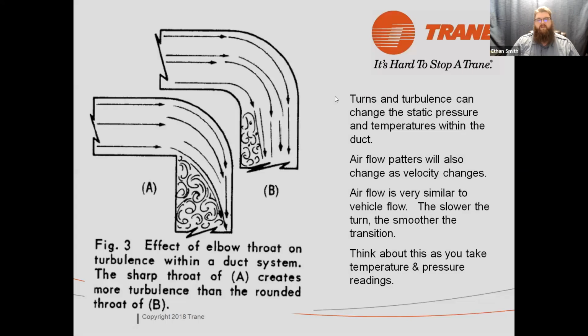Okay. It is important when you're looking at positioning those pitot tubes that you get them out of any areas of turbulence. So when you're near fittings, you want to be downstream. The general rule of thumb is you want to be 2 duct sizes downstream of any fitting or directional change in your ductwork. Of course, not all fittings are created equal, as you can see here. Swept fittings have a lower zone of turbulence versus a hard elbow fitting.